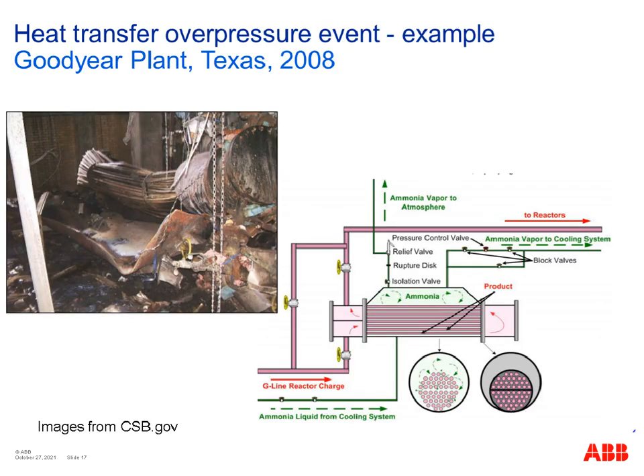So on to another case study. This is an example of an event that occurred that caused one fatality and 6 injuries. So pretty serious. Here we have a heat exchanger, and on the pink side we have the process stream, and on the green side we have the cooling stream, which is actually an ammonia stream.